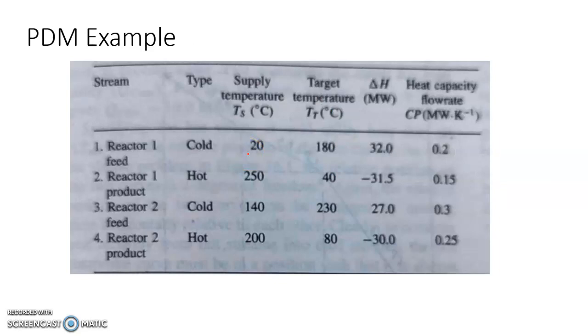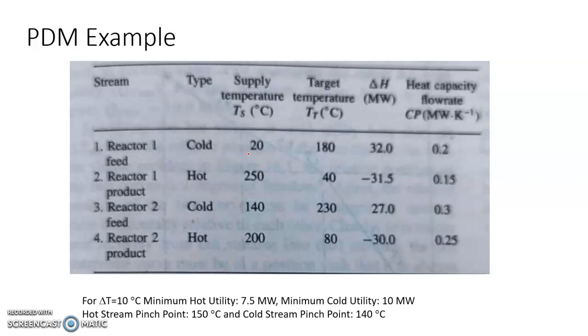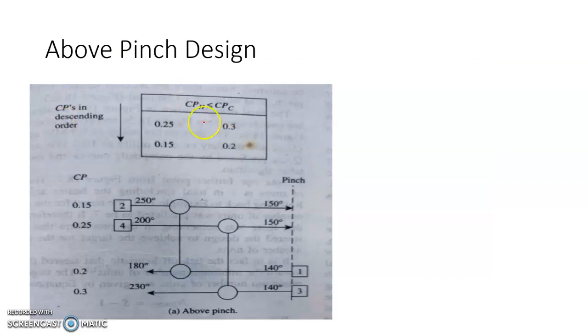Let us look at a four-stream example with two cold and two hot streams. Delta H and heat capacity flow rates are given. We first perform the problem table analysis, which gives us minimum hot utility, minimum cold utility, and the pinch temperature. With delta T minimum of 10, the minimum hot utility is 7.5 MW, cold utility is 10 MW, and the pinch point is 150°C for hot streams and 140°C for cold streams.